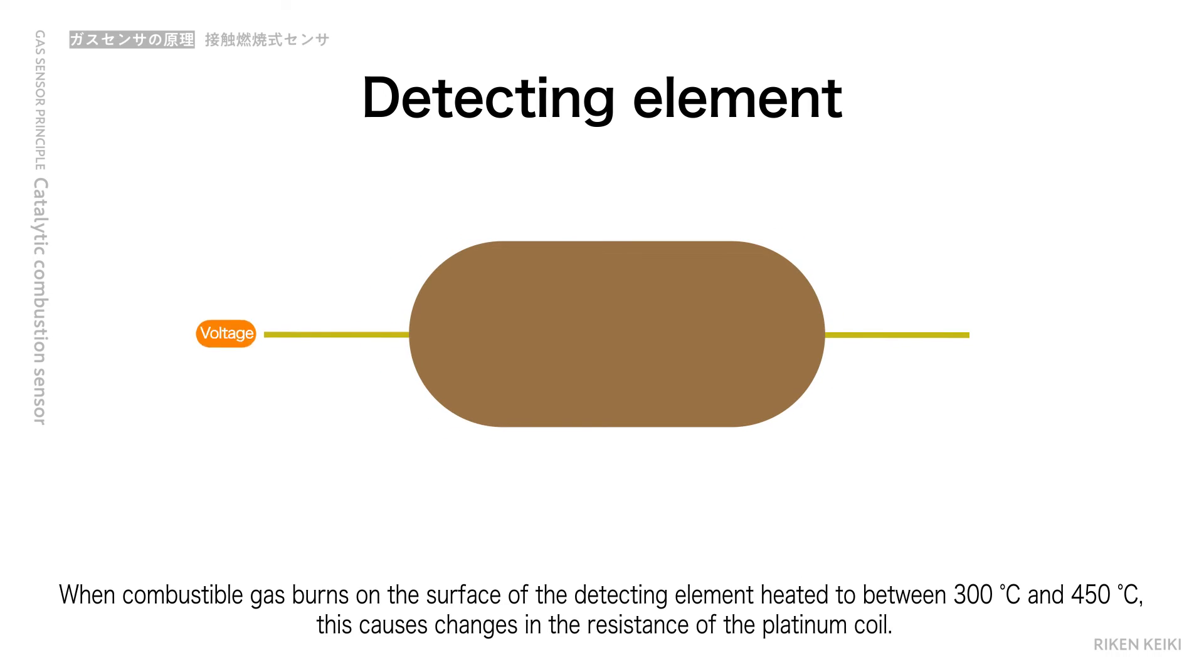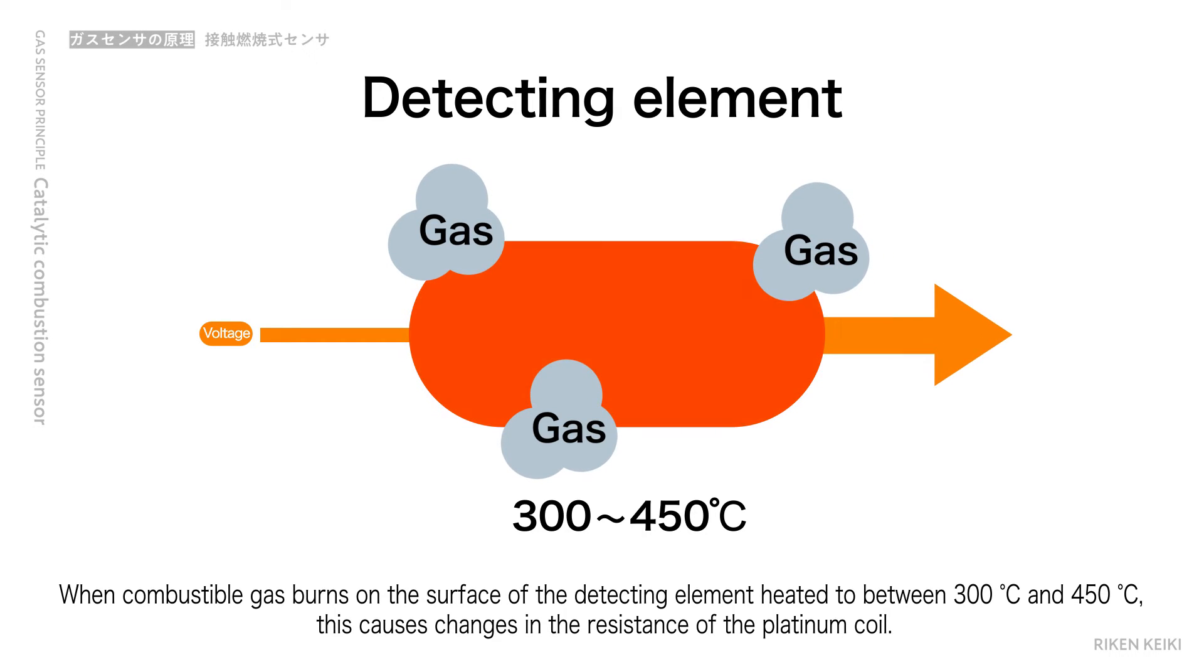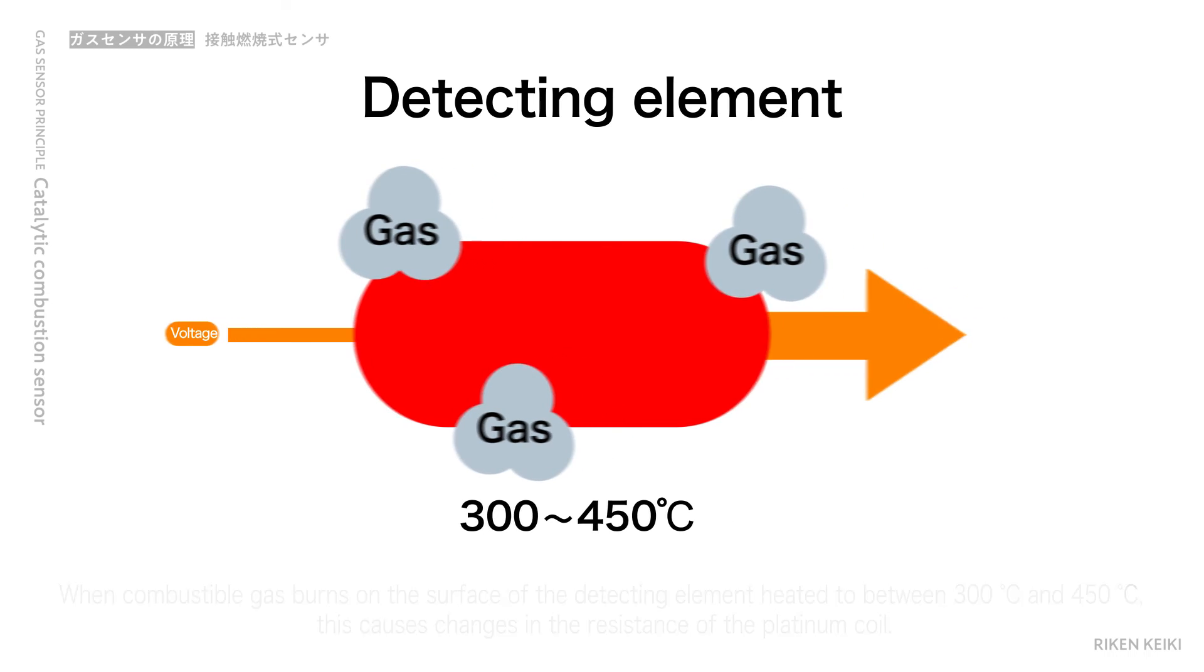When combustible gas burns on the surface of the detecting element, heated to between 300 degrees and 450 degrees, this causes changes in the resistance of the platinum coil.